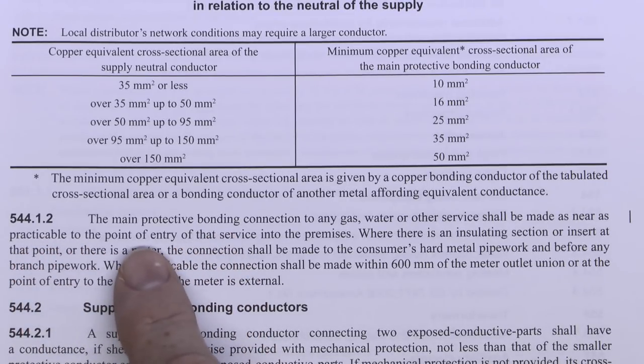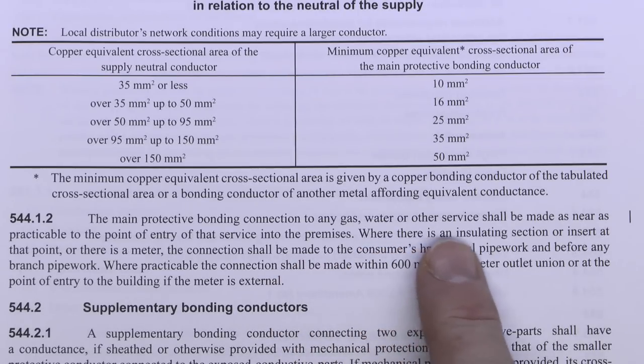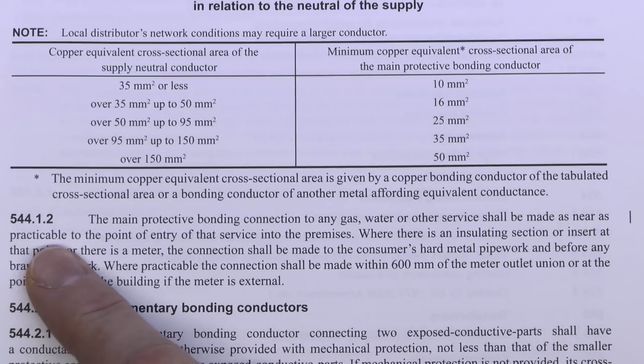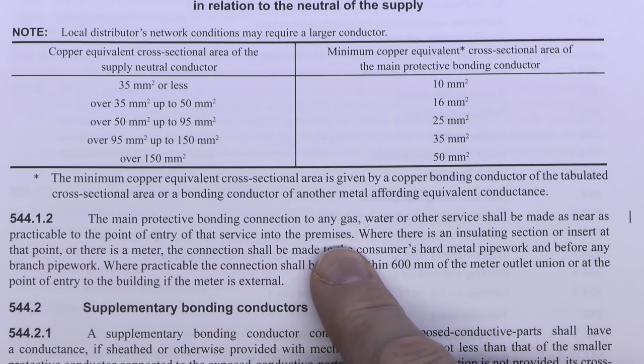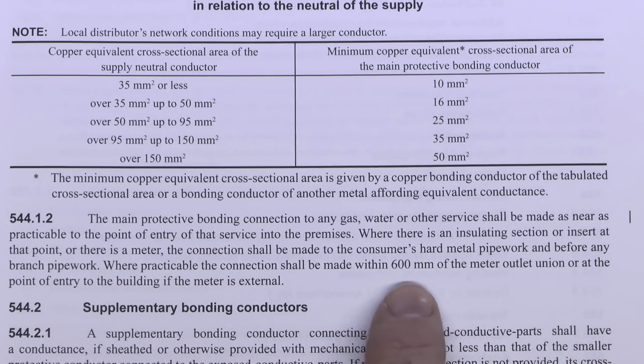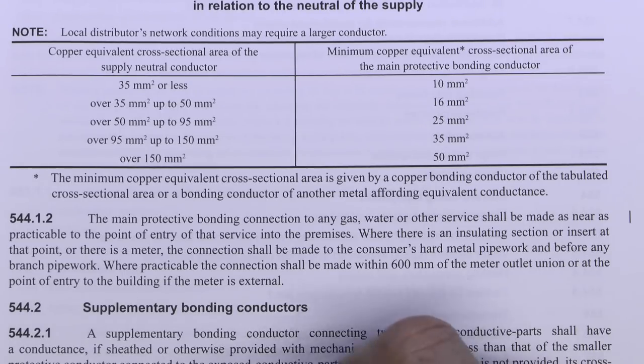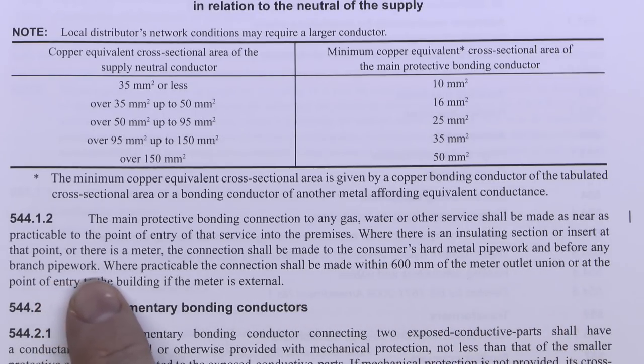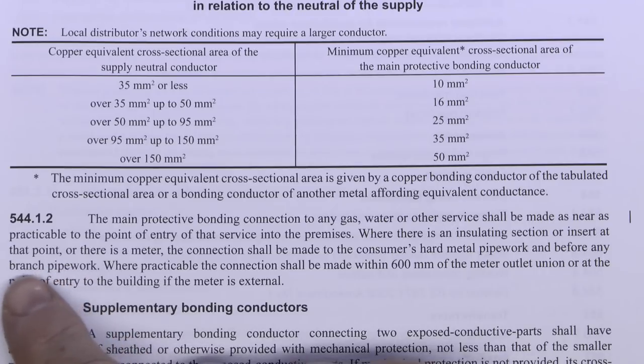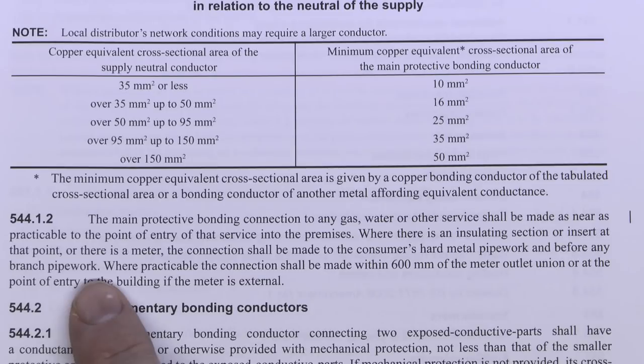The second part covers the location where the main protective bonding connection should be made. On any gas, water or other service it shall be made as near as practicable to the point of entry of that service into the premises. Where practicable it should be made within 600mm of the meter outlet, or the point of entry if the meter is external. It should also be made before any branch pipework, because if made after joints the pipework may be altered in future, potentially introducing plastic or insulating sections.